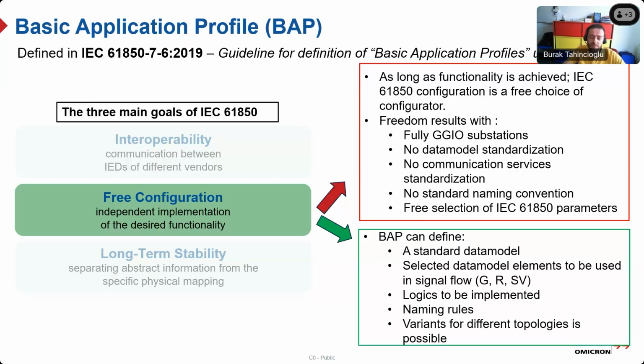In this document, a basic application profile can define a standardized data model. It will help the system integrator select the data model elements, basically the data sets in the signal flow for the services - GOOSE, report, and sampled values. The control block parameters can be defined and standardized with naming conventions. Logic can be included in this document. Naming rules can also be included to guide what to choose, what to name during the parameterization stage of 61850.